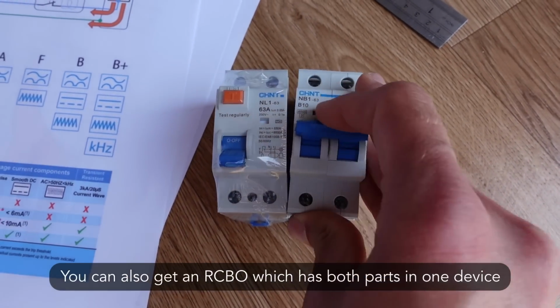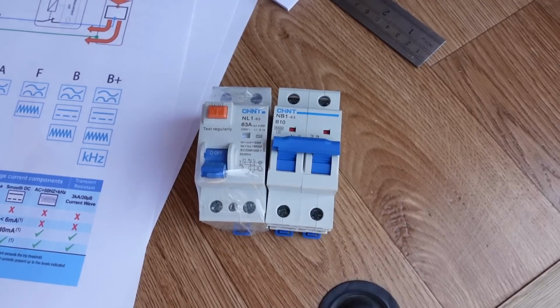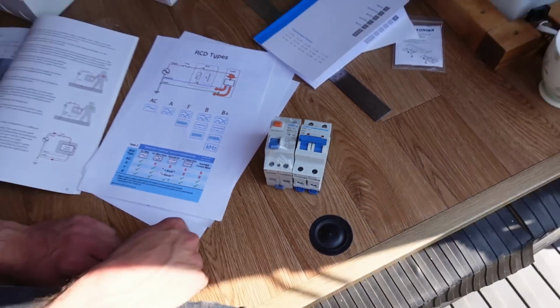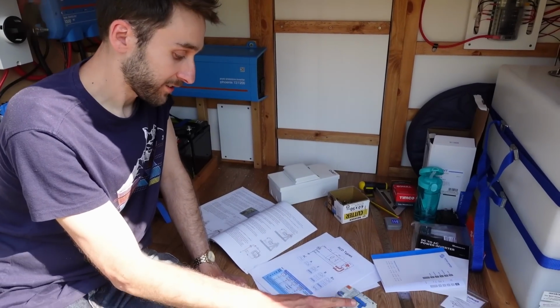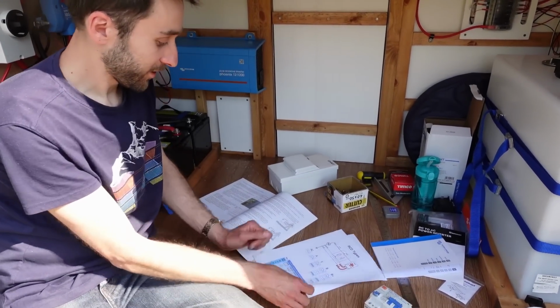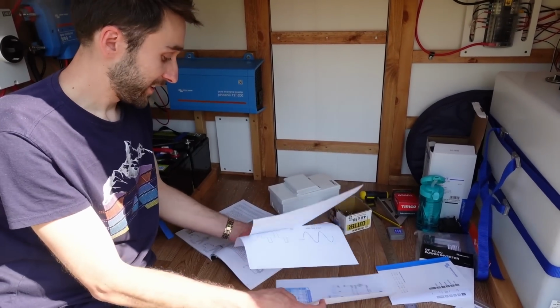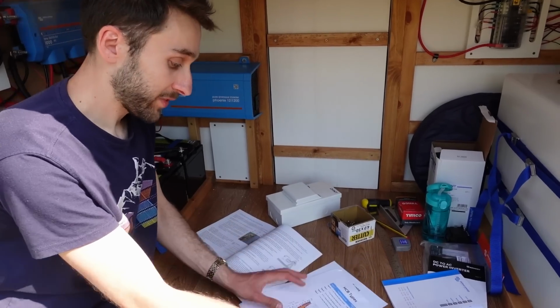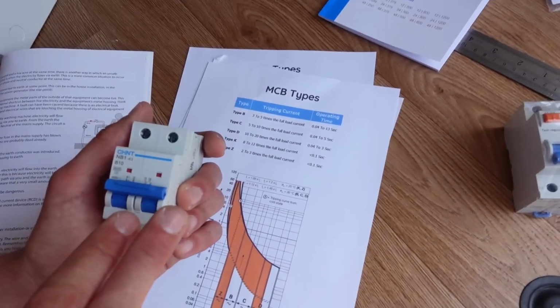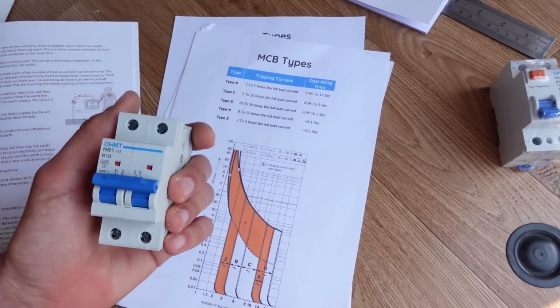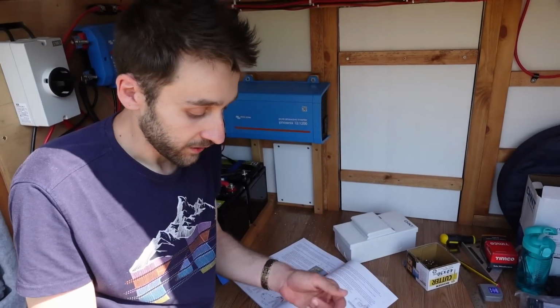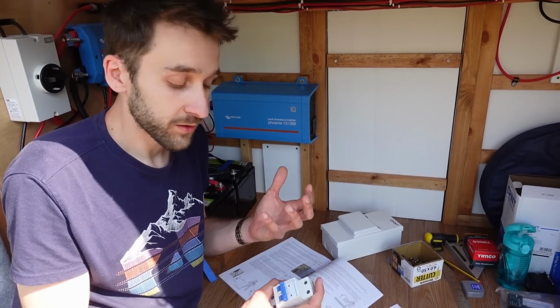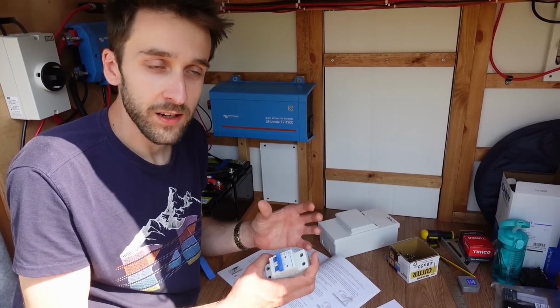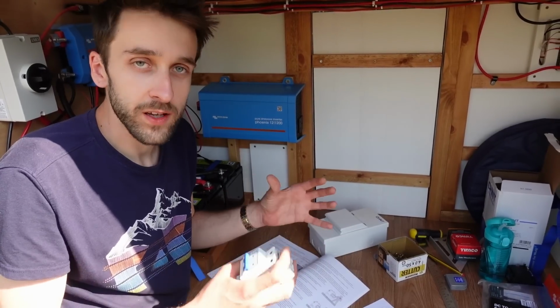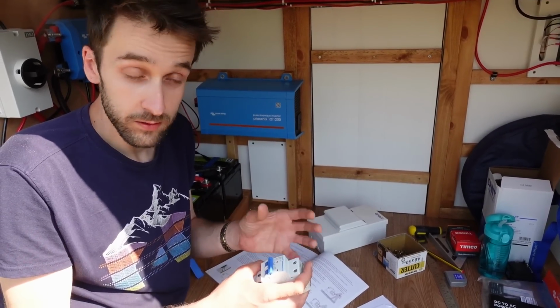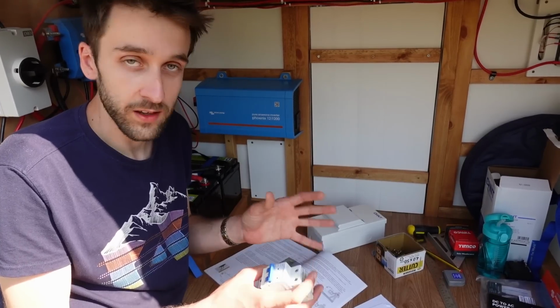This one, the MCB, is basically just like a circuit breaker. It's just like a resettable fuse, and again for that one there are different types you can get, so it all gets very confusing. But basically the way it works is there are actually two parts inside. There's a bimetallic strip which heats up when it's overloaded. So this one's rated for 10 amps, and if it goes beyond 10 amps, the strip will start to heat up, and it's not an instant thing, but if it keeps being overloaded for too long, then that strip will heat up to the point where it actually trips a switch and it cuts out.